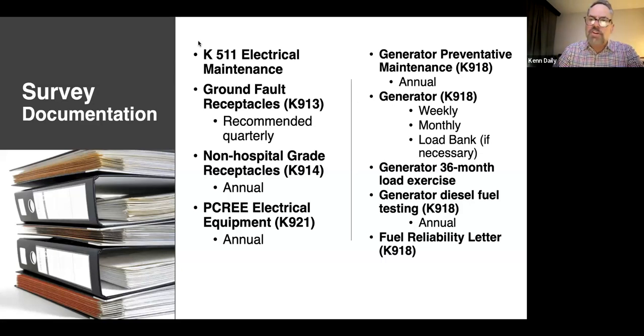A lot of surveyors in this country today walk around with a GFI tester in their hand, and if they see one while they tour your building during survey, they test it themselves, and they find a lot of GFIs that are not working. Also, sometimes they find they're not in the right locations. Typically within 6 feet of a water source, you are required to have a GFI protected receptacle.